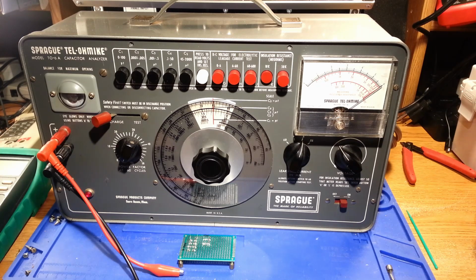I'm going to go over the first device. The first one is some of the older capacitor testers, the older vintage ones. This one I have in view now is a Sprague TO6A capacitor tester, along with being able to test values on capacitors and power factor, which is kind of the first version of checking ESR on electrolytic capacitors. This meter is capable of measuring resistive faults out to 50 kilo megaohms, or what would translate to 50 gigaohms.